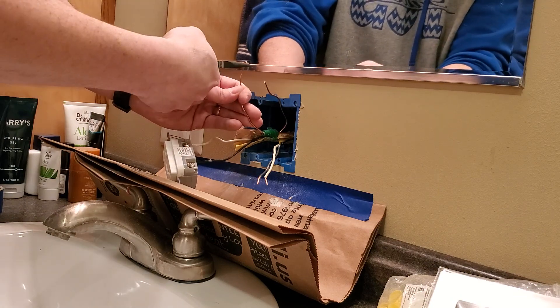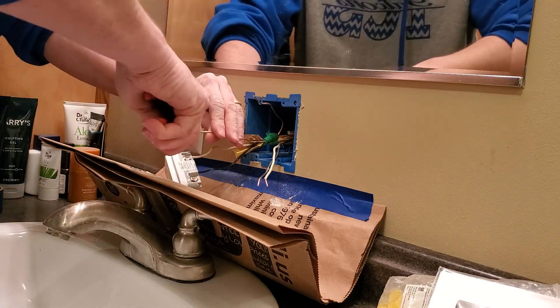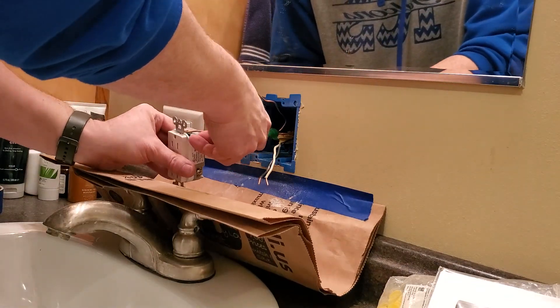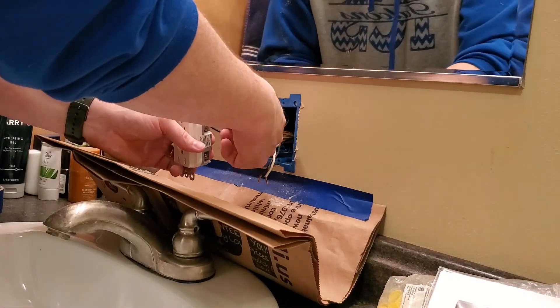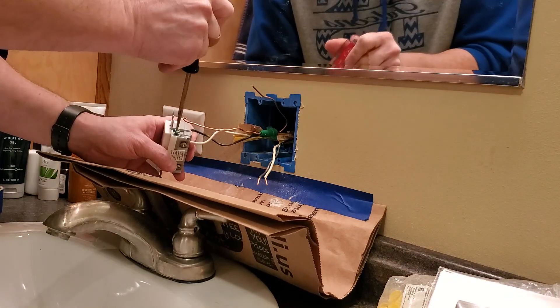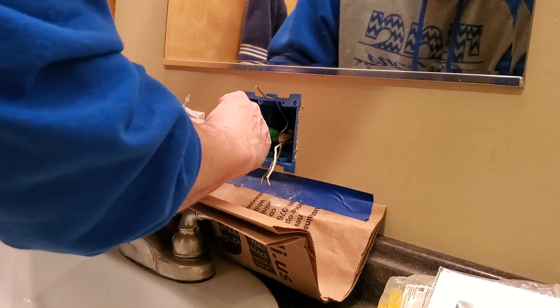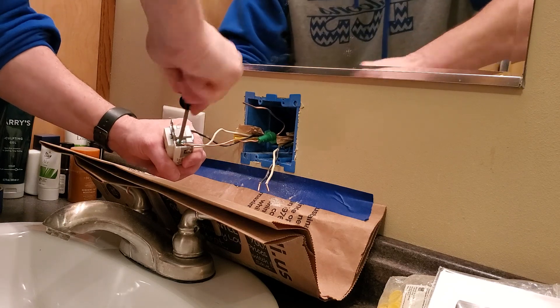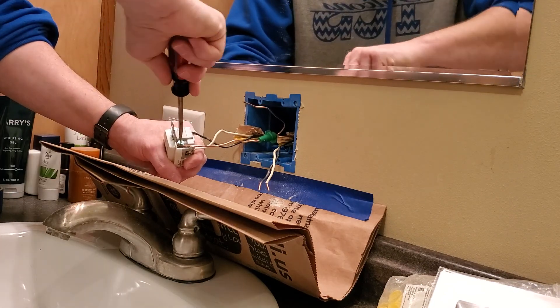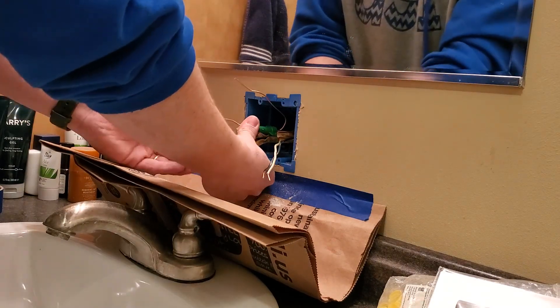I've got a nice little hook to hook around that screw. I'm going to tilt that down just a little bit to help hook it on there — it is in a tight place. There we go, popped right in there. As I snug this up it's going to pull that wire in going clockwise around it — if I put it the other way it'd push it out.